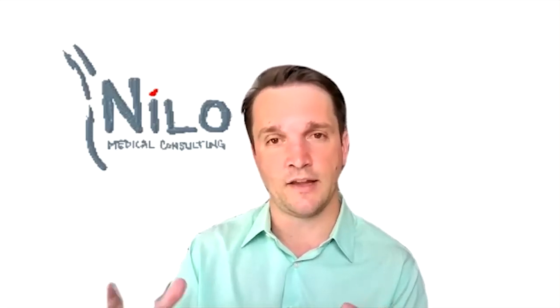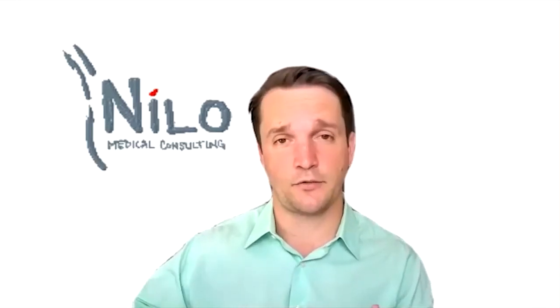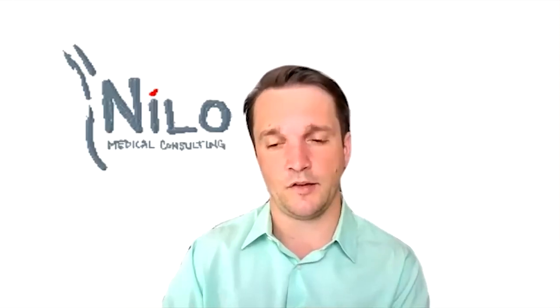definition, FDA says these are three things. They're non-medical device. They are medical device that the FDA is not going to enforce the regulation requirements on because they're too low risk or too common to worry about. The doctors are still handling all this, and the FDA doesn't need to worry about regulating them. Or there are clinical decision support applications that are regulated, and you need to go through the class 1, class 2, or class 3 process associated with it.